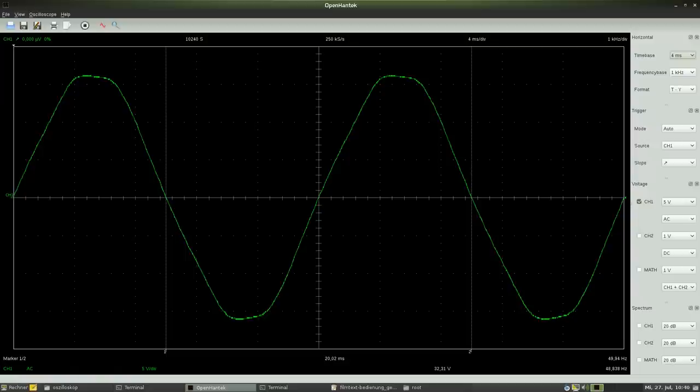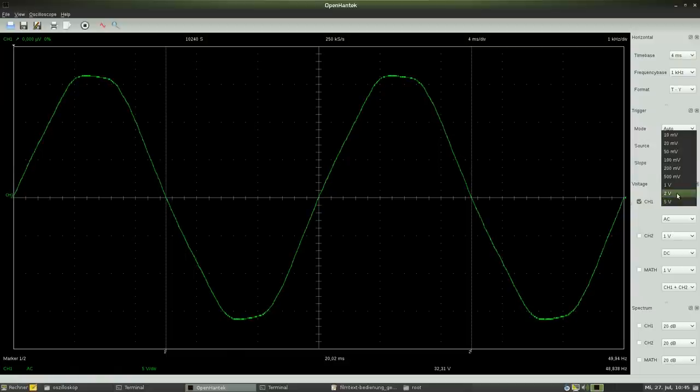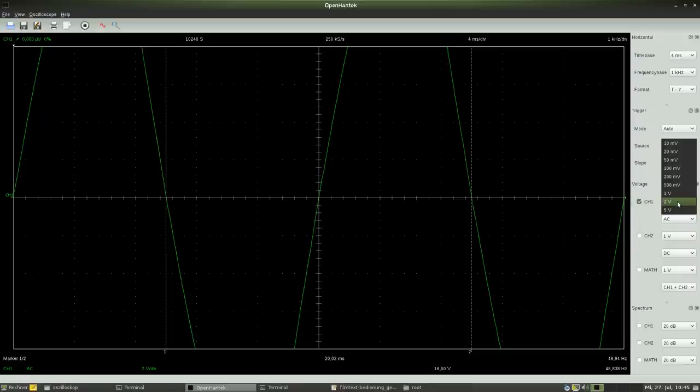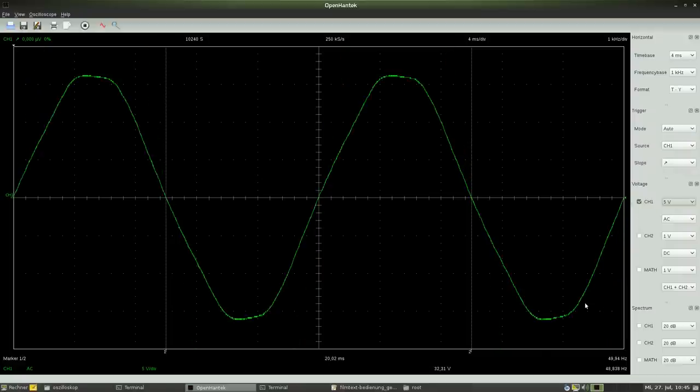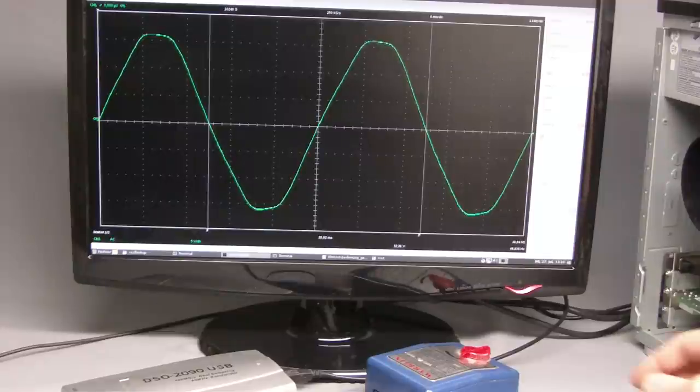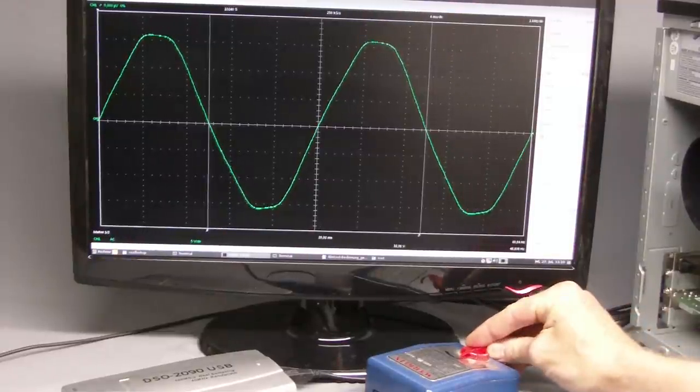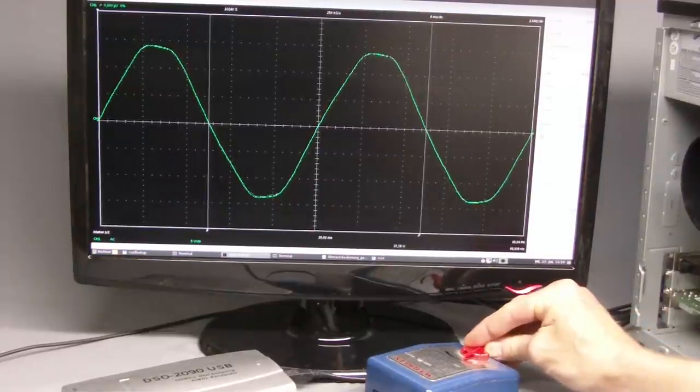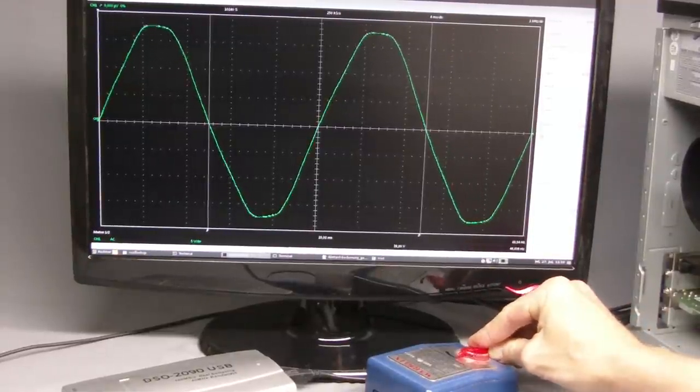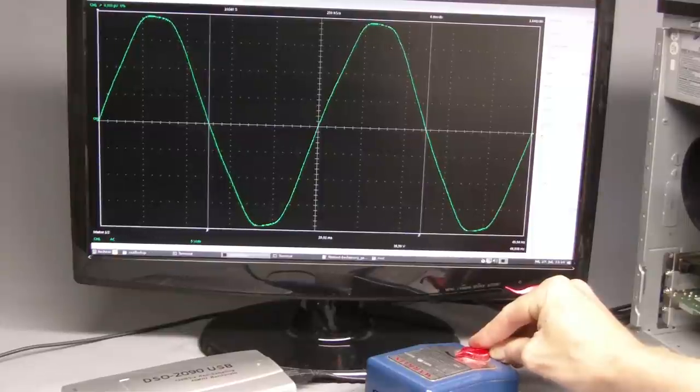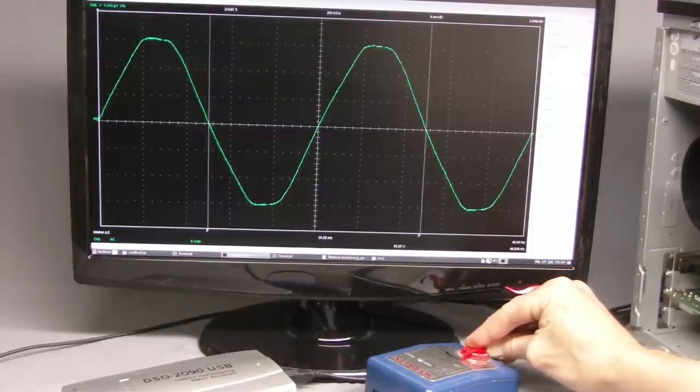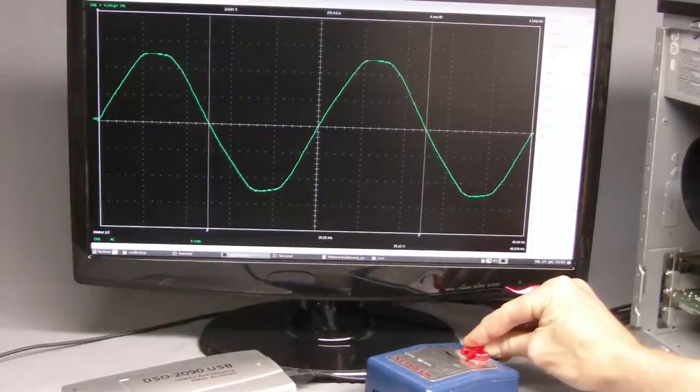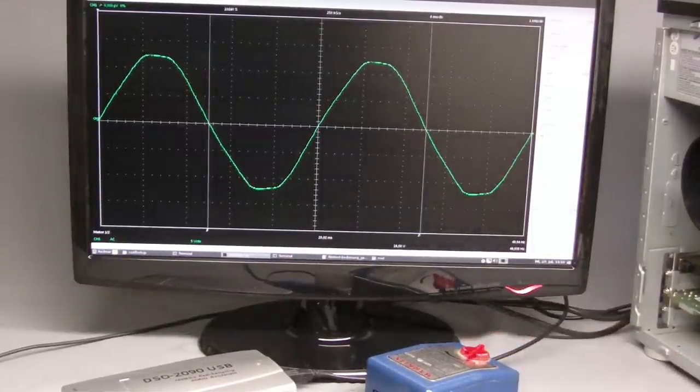If we decrease the vertical scale down to 2V per division, the peaks of the sine curve are out of the adjusted range. The measurement of the AC voltage is automatically repeated, by which we can see the peak to peak voltage increasing as soon as I'm turning the actuator of the transformer.